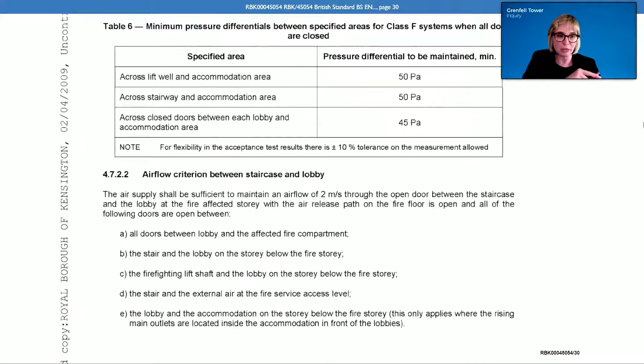So these are the kind of scenarios, when we were talking about scenarios before, that we don't see any analysis of. And in the testing that's done, we don't see any testing that's done with different doors open to check that the system can still cope in those situations, or at least test what the system does in those scenarios. Do you agree? No, basically. But I can see where you're leading. The technical submittal proposed the 2 metres a second airflow test in accordance with this standard. So my expectation is it will be tested in accordance with this test procedure and opening and closing the relevant doors to the Class B system. So that's clearly stated in the technical submittal.